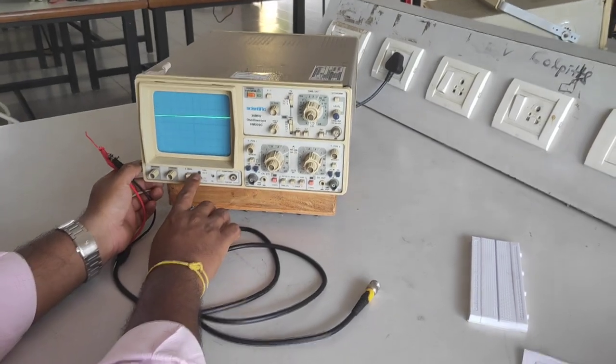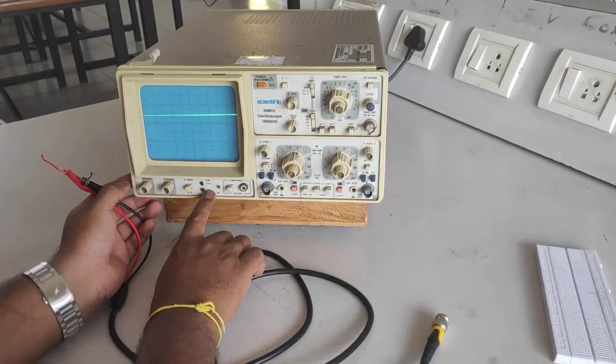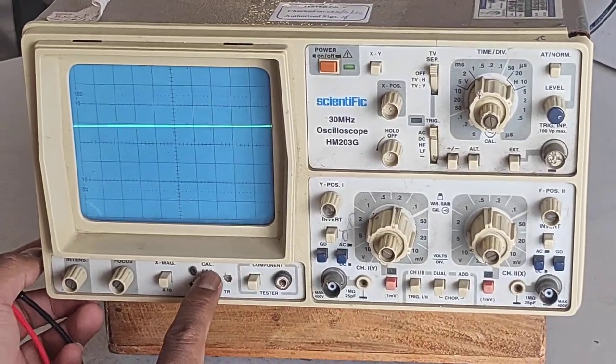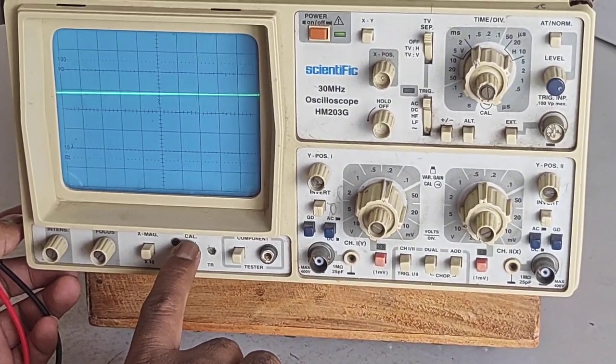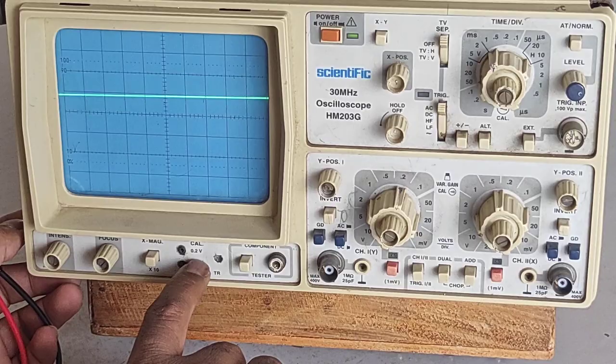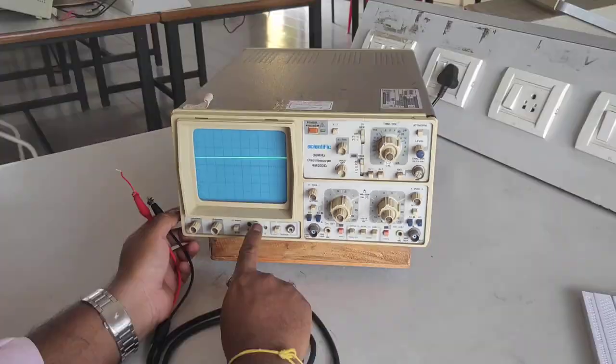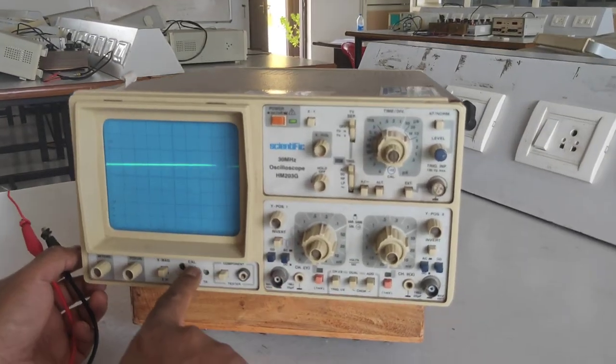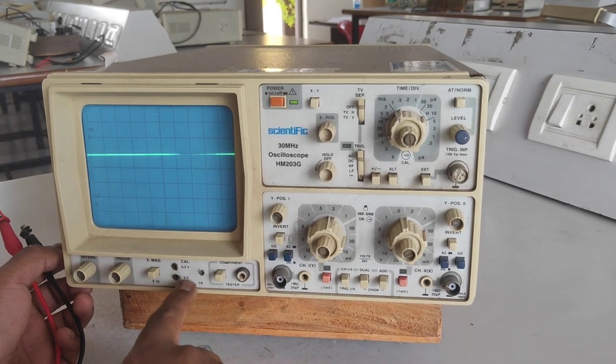On every oscilloscope, you can find calibration points available on the front screen. On every CRO, it will be mandatory - the company will provide this. The main purpose of why they have given this is to check whether your CRO is calibrated and whether it is giving accurate measurement. Before starting any measurement, if it is available, you check.